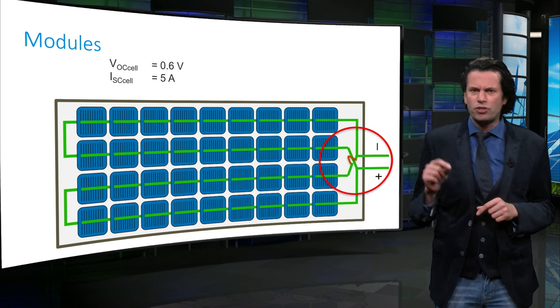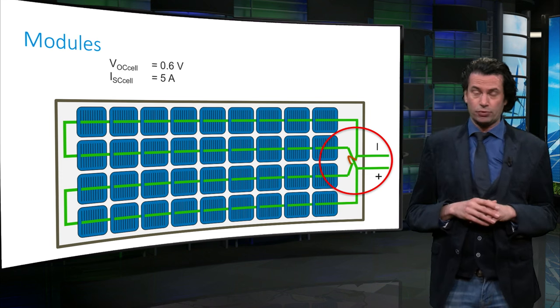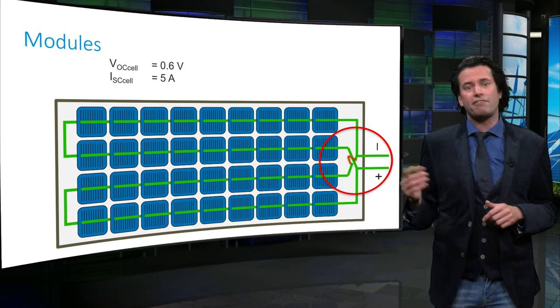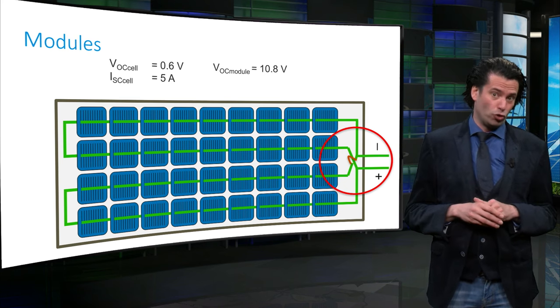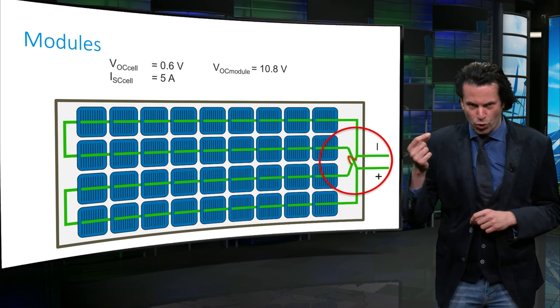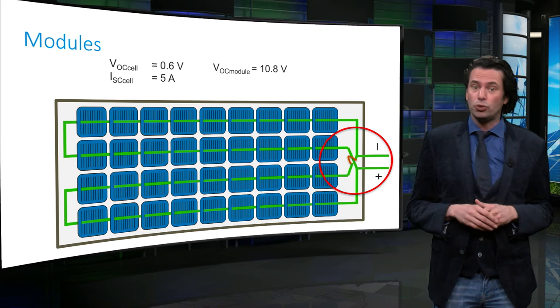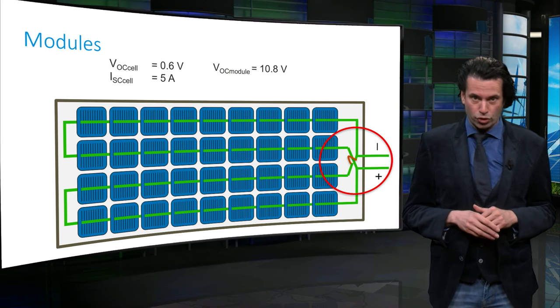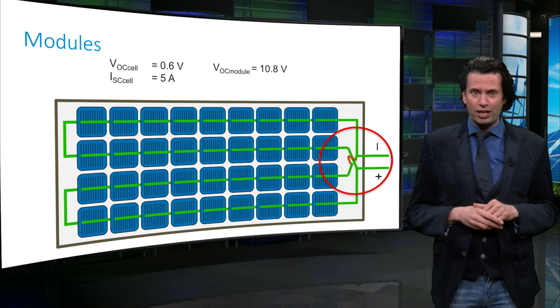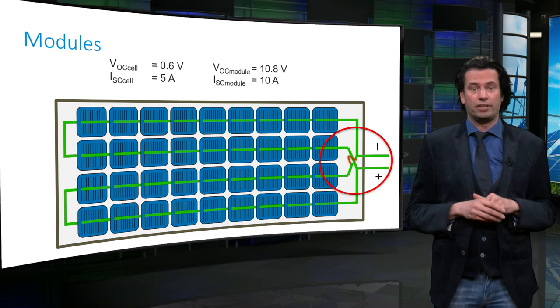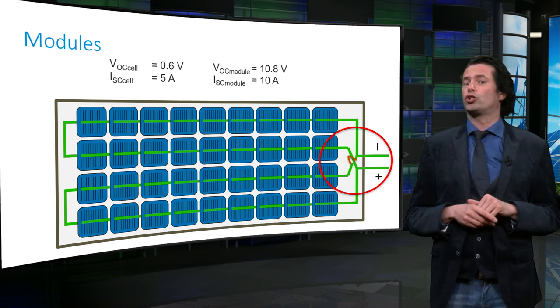This gives us 10.8V for the open-circuit voltage. As we have two rows in parallel, we have to multiply the short-circuit current by 2 to get the module short-circuit current. If we do this, we get 10A for the module short-circuit current.